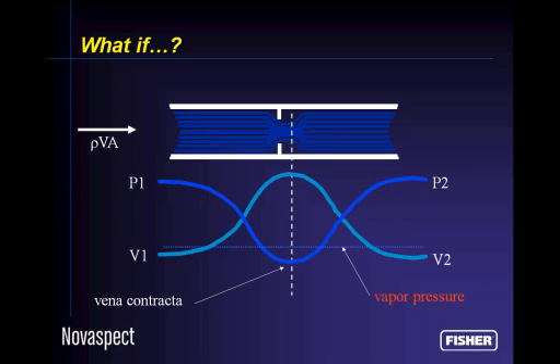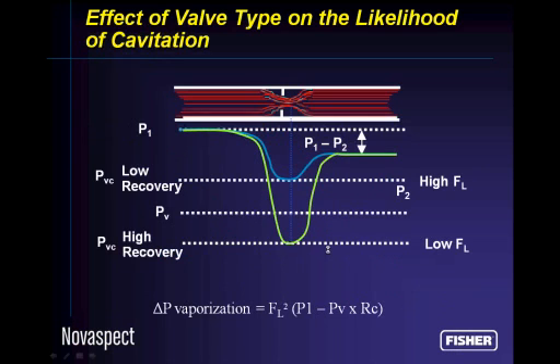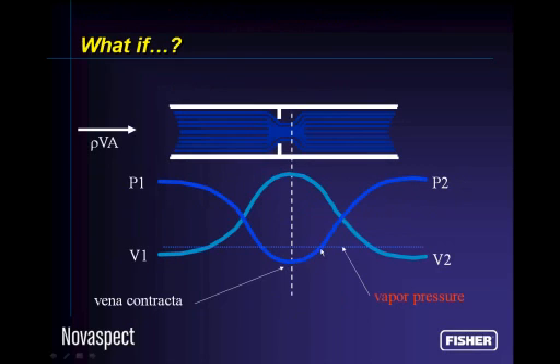So what if it just happens that this dip in pressure in the middle of our control valve drops below the vapor pressure? That is a very important phenomenon to know is going to occur, because as the pressure drops below the vapor pressure, the fluid, the liquid, whatever it was, starts to boil. And it's boiling all through this trip through the control valve until it recovers to a pressure, P2, higher than the vapor pressure. And as soon as it crosses that vapor pressure, all of those vapor bubbles, if it were water, what we've got is a bunch of steam in here.